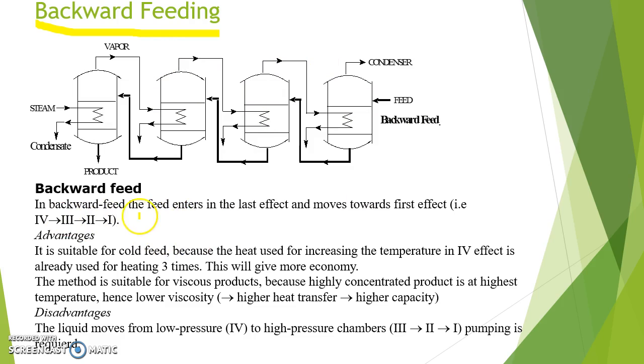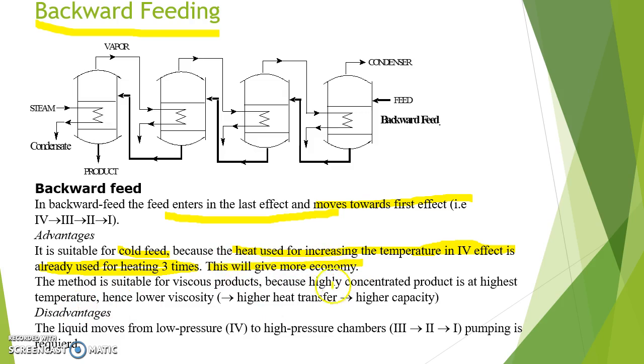In backward feeding, the feed enters the last effect and moves towards the first effect. The advantage of this method is that it is suitable for cold feed, because the heat used for increasing the temperature in the fourth effect has already been used for heating three times, giving more economy. This method is also suitable for viscous products because the highly concentrated product is at the highest temperature, hence it has lower viscosity.